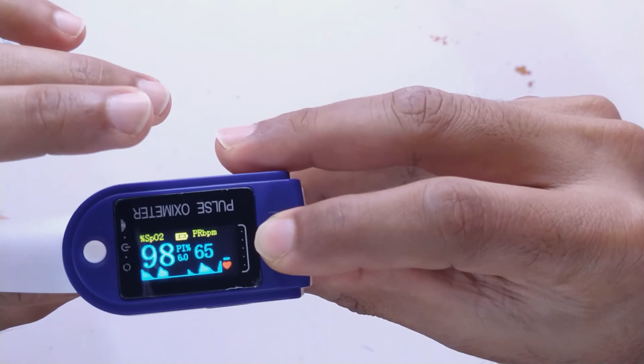Let's cut some white paper and put it in the pulse oximeter and see. Fold the white paper and wrap it around my finger and put it in the pulse oximeter, and let's check if it gives some reading. No reading. Yeah, reading is coming, 98%, and pulse rate is 69. Since paper is semi-transparent, the light comes out of the paper and gives a result. Yeah, it is the previous result.